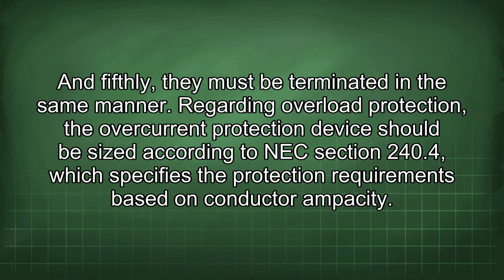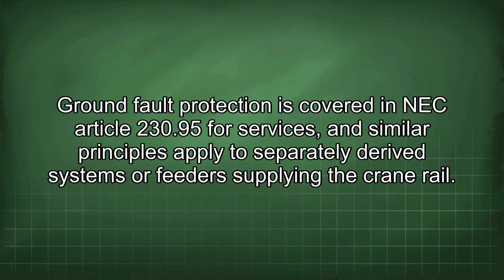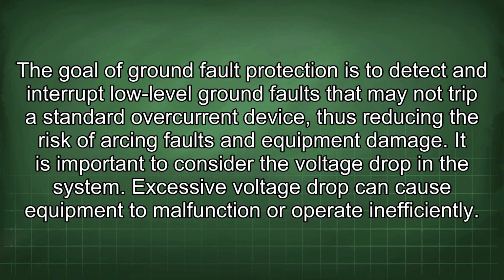Regarding overload protection, the overcurrent protection device should be sized according to NEC Section 240.4, which specifies the protection requirements based on conductor ampacity. Ground fault protection is covered in NEC Article 230.95 for services, and similar principles apply to separately derived systems or feeders supplying the crane rail. The goal of ground fault protection is to detect and interrupt low-level ground faults that may not trip a standard overcurrent device.